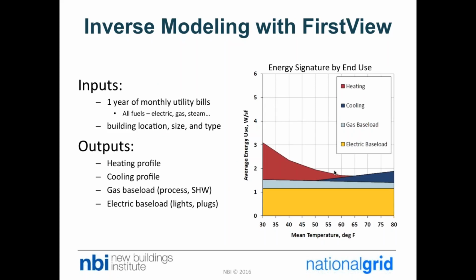So if you look at the right, this is called an energy signature. It shows how much energy the building is using at various temperatures. You can see that the red is the slope for heating, and as the temperature rises, less and less energy is needed for heating, and as it continues to rise, you begin to see the need for cooling in the building. And of course, some loads are fairly constant over the course of the year.